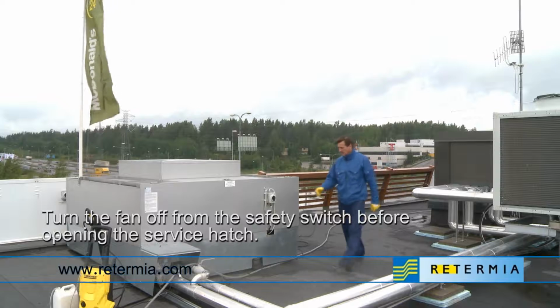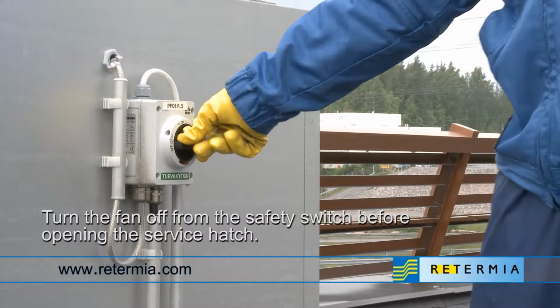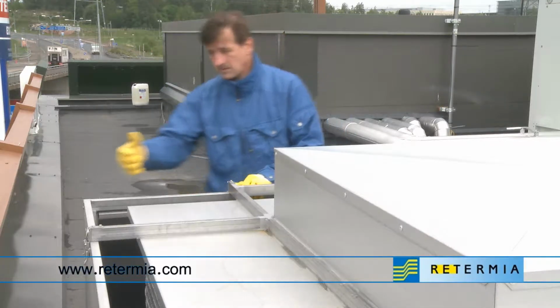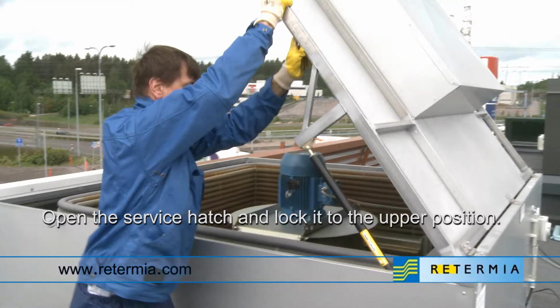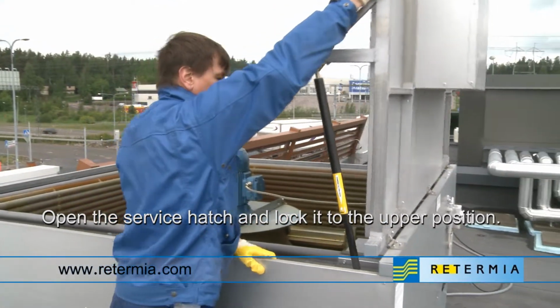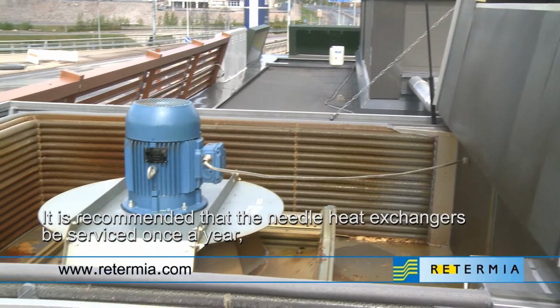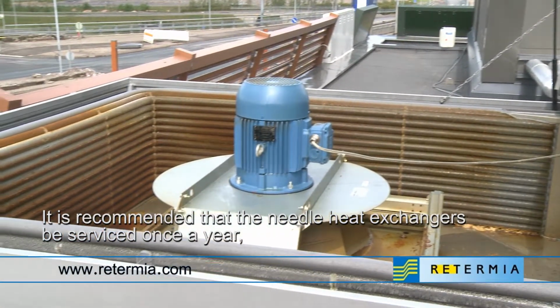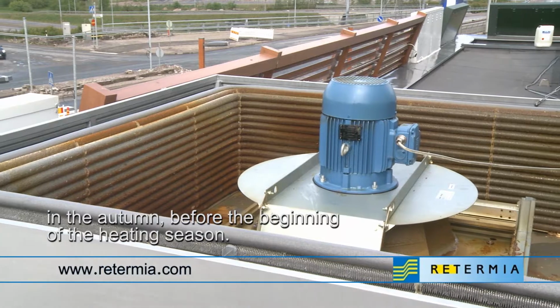Turn the fan off from the safety switch before opening the service hatch. Open the service hatch and lock it to the upper position.